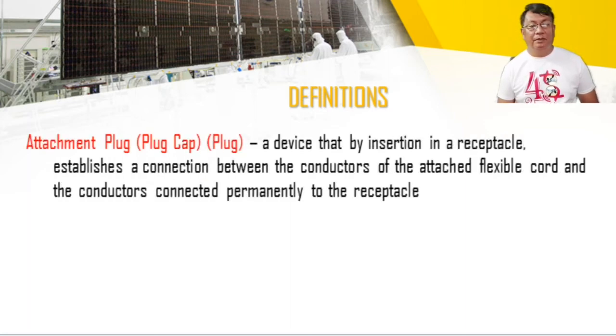Let's continue with the definitions. The definitions here are for some important terminologies only, not all. We have several definitions in the Philippine Electrical Code, but what I included here are some of the basic or common terms that you might always encounter in the implementation of this code. The first one here is attachment plug, plug cap, or just simply plug. It is a device which, by insertion in a receptacle, establishes a connection between the conductors of the attached flexible cord and the conductors connected permanently to the receptacle. That is what we call an attachment plug, plug cap, or just simply plug.